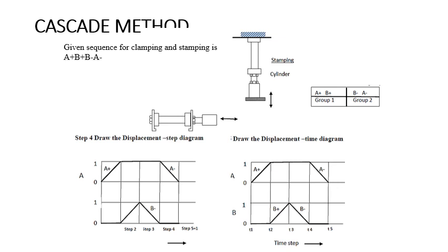In the previous video we observed the signal conflict. The signal conflict occurs to achieve the sequence A-plus, B-plus, B-minus, A-minus. The memory valve — a double pilot-operated memory valve — is getting a signal at a time from both sides, making it difficult to switch over. That signal conflict is going to be avoided by using the cascade method. To eliminate the signal conflict, the cascade method was introduced.